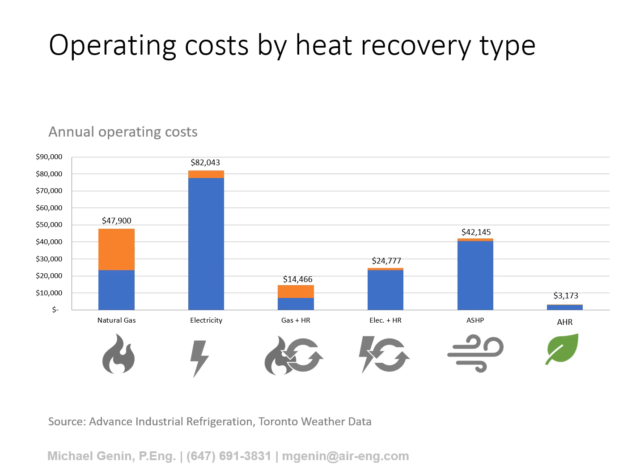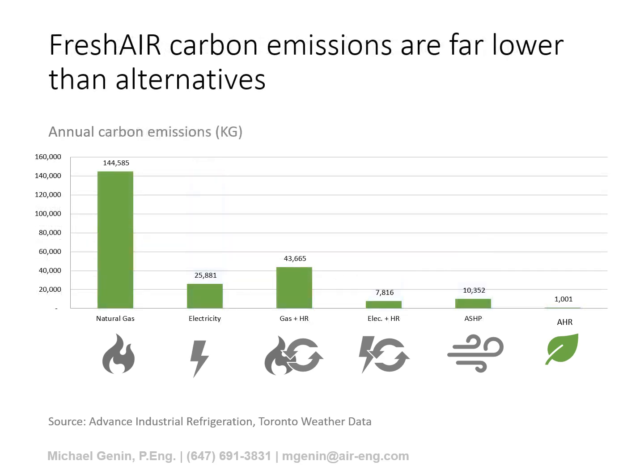You can see there is a substantial reduction in the operating costs with active heat recovery that mainly stems from the extremely high coefficient of performance, or COP, you get from using exhaust air as a source. And then how does this example shake out in terms of carbon emissions? This is using the carbon intensity of the Ontario electric grid, which is relatively clean. So natural gas is over 144,000 kilograms, electricity 25,000 kilograms, and then we have gas plus heat recovery, electric plus heat recovery, passive devices. Air source heat pump is similar to using an electric element plus a heat recovery device, and then we have active heat recovery. Again, the lowest carbon impact device when compared to all other types of heat recovery.